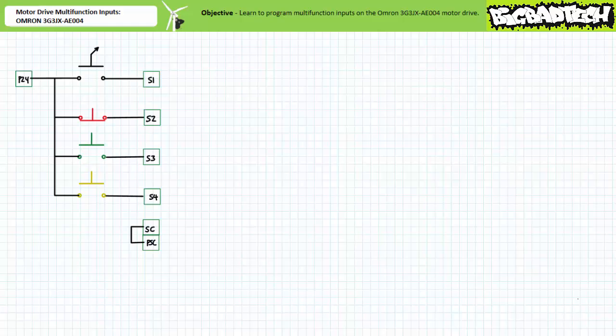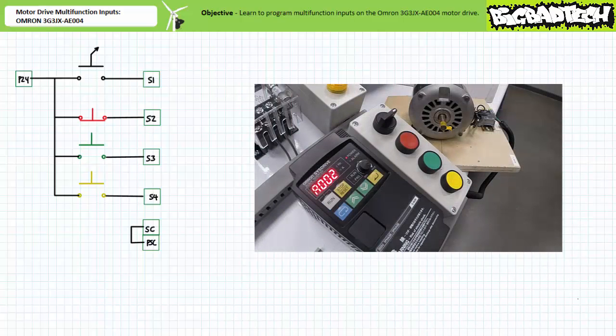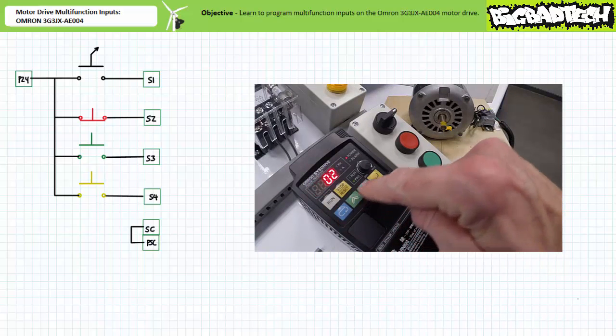The far more appropriate way to program this drive is to first assign the desired function to the appropriate inputs, then hand off operation from the digital operator group to the multifunction input terminals. This way the drive executes the desired functions right out of the gate and we're less likely to get a valuable portion of our anatomy ripped off should this motor unexpectedly spring to life. Let's go about this in the proper manner. Ensure extended function parameter A002, run command selection, is in the default state of 02 — direct operation via the run and stop/reset button in the digital operator group.